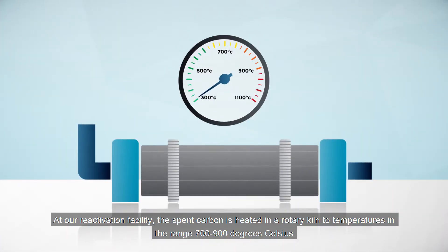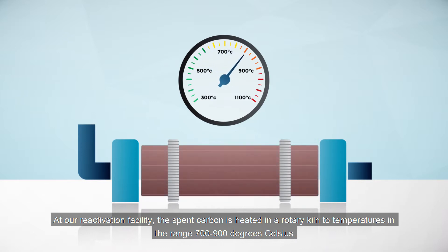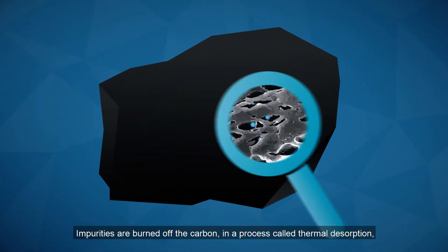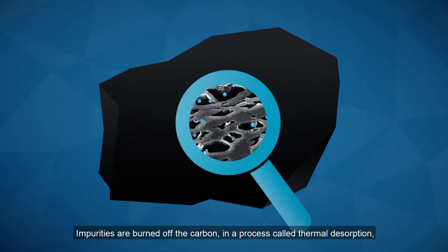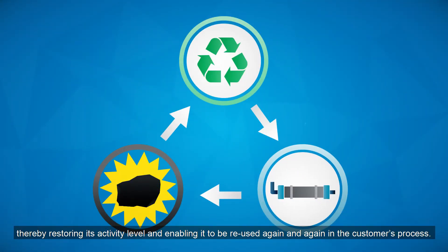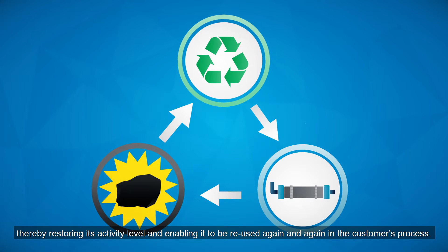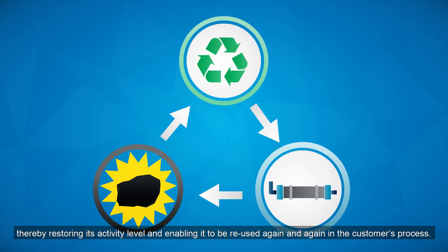At our reactivation facility, the spent carbon is heated in a rotary kiln to temperatures in the range of 700 to 900 degrees Celsius. Impurities are burned off the carbon in a process called thermal desorption, thereby restoring its activity level and enabling it to be reused again and again in the customer's process.